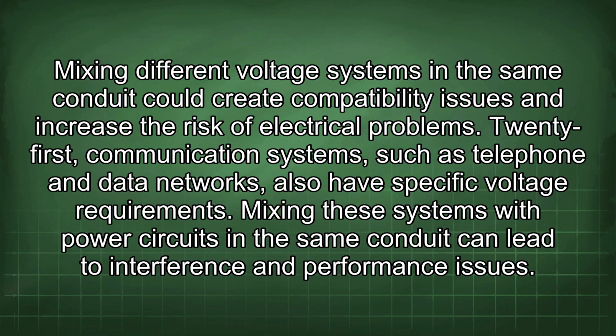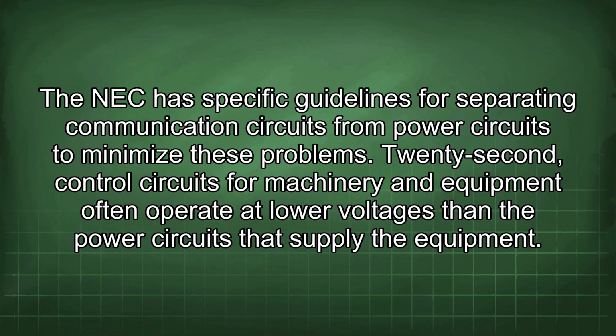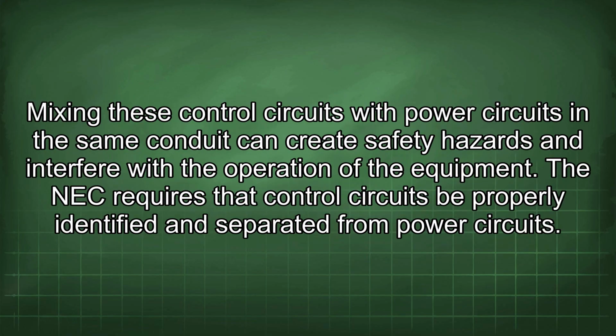21st, communication systems such as telephone and data networks also have specific voltage requirements. Mixing these systems with power circuits in the same conduit can lead to interference and performance issues. The NEC has specific guidelines for separating communication circuits from power circuits to minimize these problems. 22nd, control circuits for machinery and equipment often operate at lower voltages than the power circuits that supply the equipment. Mixing these control circuits with power circuits in the same conduit can create safety hazards and interfere with the operation of the equipment. The NEC requires that control circuits be properly identified and separated from power circuits.